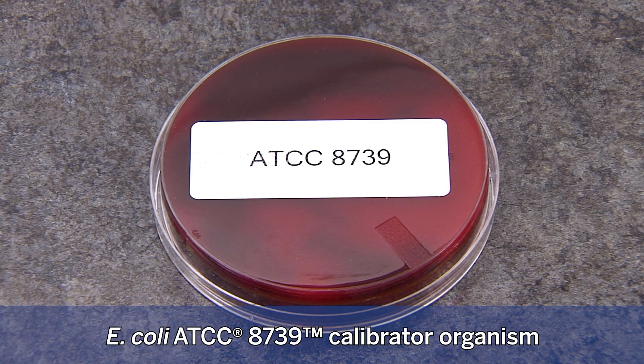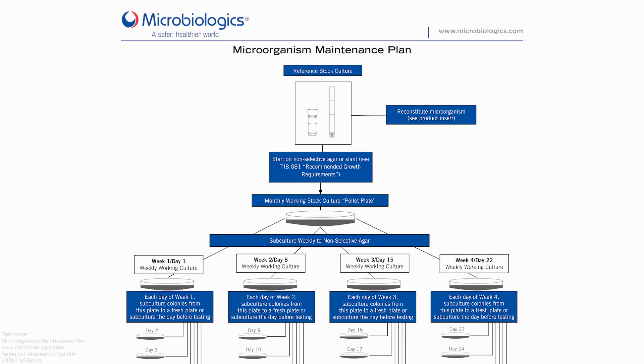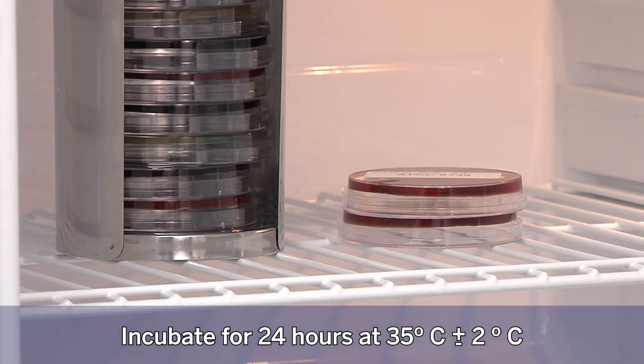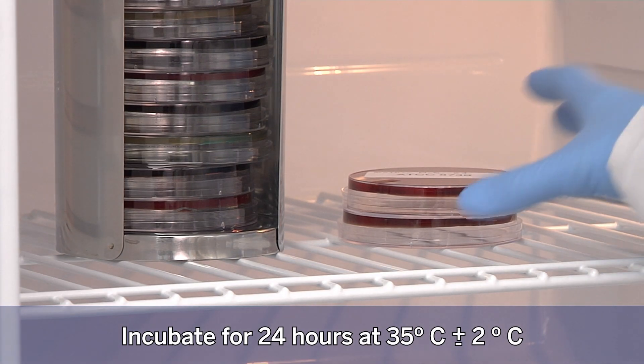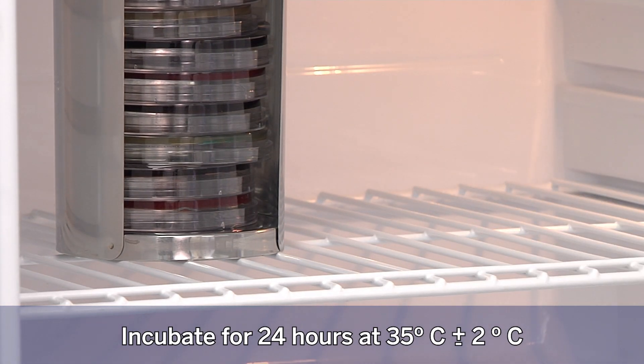E. coli ATCC 8739 is used as the calibration strain. Reconstitute a purchased stock strain according to the manufacturer's directions. As an example, the Microbiologics package insert details a microorganism maintenance plan. A stock culture plate is inoculated from the reference stock using trypticase soy agar with 5% sheep blood or Columbia agar with 5% sheep blood. This stock plate is incubated for 24 hours at 35 degrees Celsius plus or minus 2 degrees Celsius, and will be used for subculture for 4 weeks, after which it is discarded and a new stock plate is made from another reference stock culture.